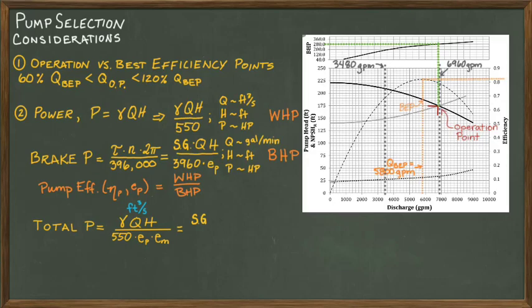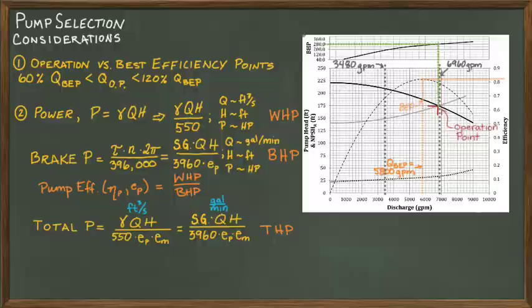Anywho, if we wanted to know the total horsepower to run the pump, then we must also account for the motor's efficiency. Put another way, power comes to our motor from the wall. The motor converts the electrical power into mechanical power by turning the pump shaft. As you can imagine, there are losses in this conversion process similar to the losses observed when transferring power from the pump shaft to the fluid, and those losses are accounted for in the E_M term shown here.